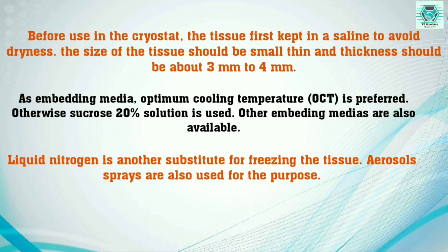After handling, embedding is done. For other microtomes, paraffin is mostly used as embedding media, but here the OCT (optimum cutting temperature) compound actually works as embedding media, or a 20% sucrose solution can be used. Other embedding media are also available for the cryostat. Liquid nitrogen is another substance used for freezing the tissue, and expertise is required while using it to get uniform freezing. Aerosol sprays are also used for this purpose.